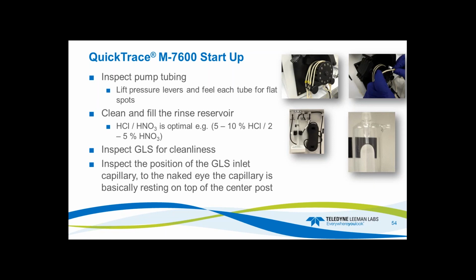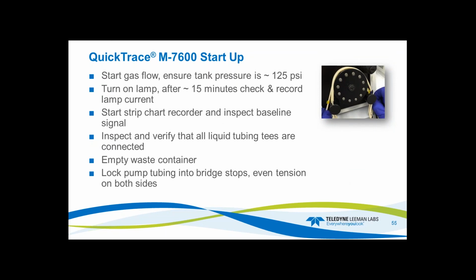So inspect the GLS for cleanliness, inspect the position of the capillary, and to the naked eye it should look pretty much right on top of the center post. So once that's all set, you can make sure the tank pressure is set to approximately 125 psi. Turn the lamp on. After 15 minutes you can go into the instrument controls, record the lamp current in a logbook, start the strip chart recorder, inspect the baseline, make sure everything's fine there, make sure that all your tubing tees and everything is connected, empty the waste container, and then lock the pump tubing into the bridge stop. So even tension on both sides and into the first bridge stop.